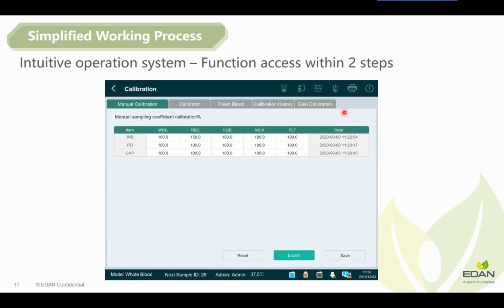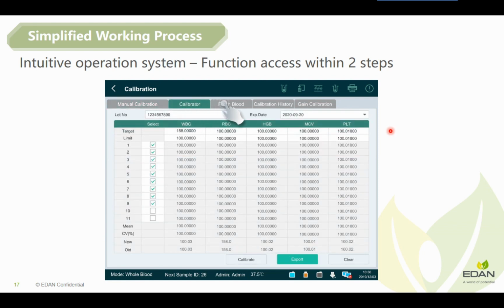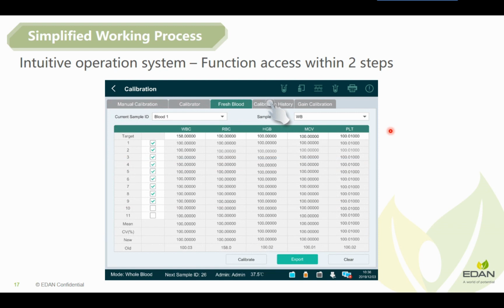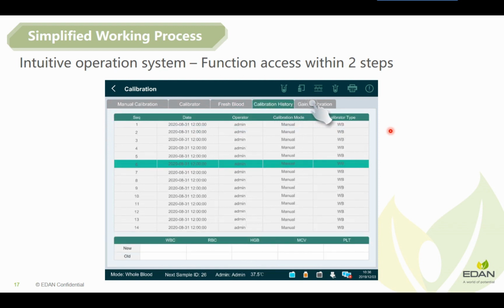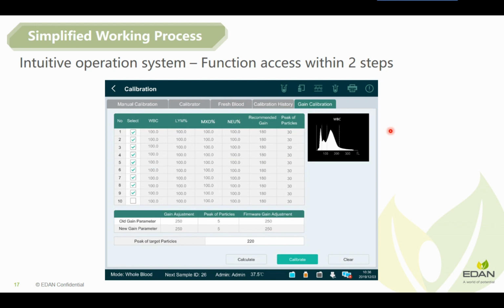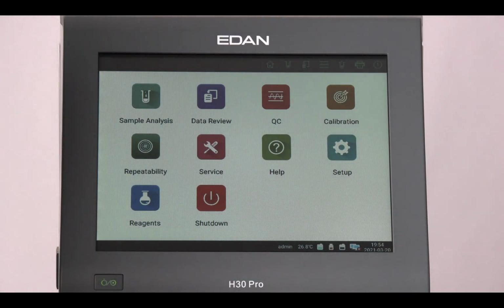We also try to reduce the complexity of the software and enhance the interaction experience between users and the system. The H30 Pro always requires only 2 steps to access any function. The calibration page is a good example. There are 5 subtabs under calibration, including manual calibration, auto calibration, fresh blood, and so on. But once you enter the calibration page, you can get access to all the subtabs with a simple click, and then you access the target one. See, it's very easy to locate the function page, right?